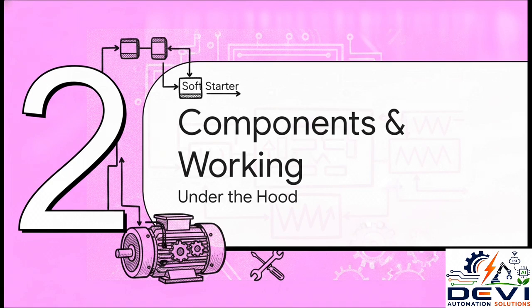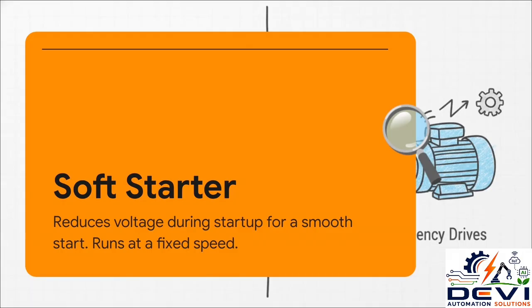Moving on to Section 2, Components and Working Principles. Let's look under the hood. First up is the soft starter. Think of this as a device that intentionally and temporarily holds back the electrical voltage during a motor's startup phase. By doing this, it provides a really nice smooth ramp-up, which significantly cuts down on both mechanical wear and electrical stress. Now, the core components pulling this off are the SCRs, or thyristors, which act kind of like electronic valves for the voltage. You've also got a heatsink to manage temperatures and a bypass contactor. But, and this is a vital detail to remember, once the motor is fully up and running, a soft starter runs it at a fixed, constant speed.